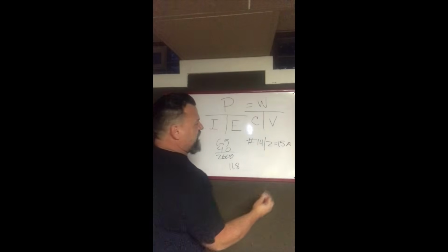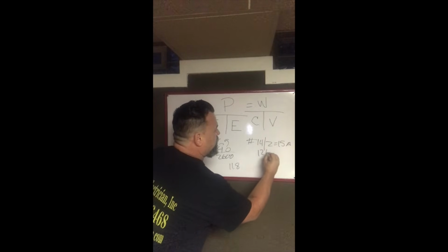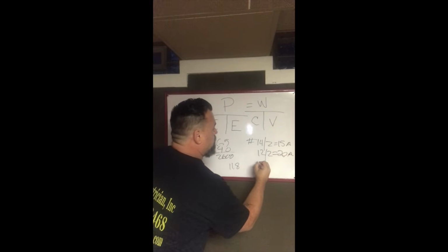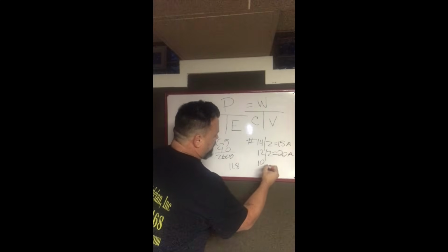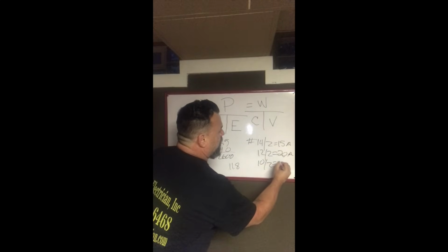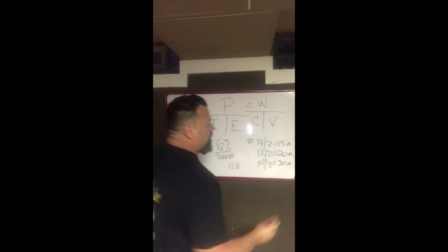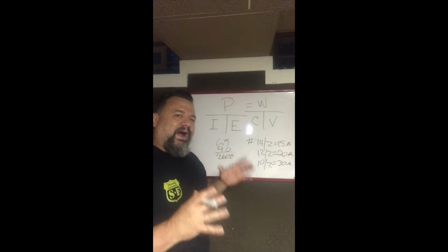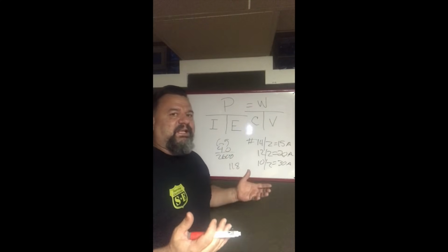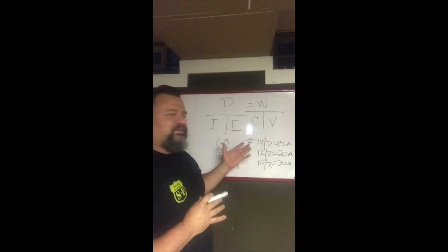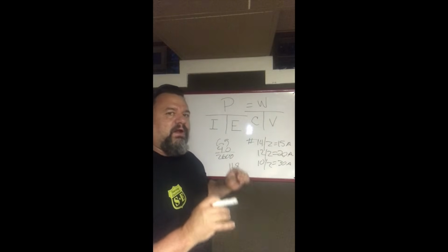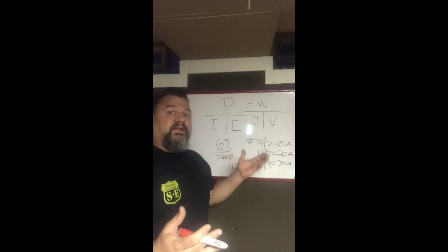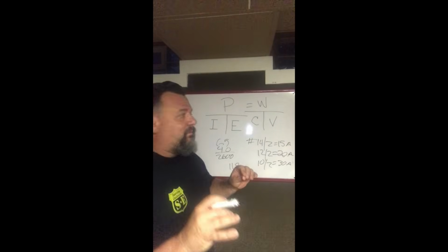Now, 14.2 is good for 15 amps. 12.2 is good for 20 amps. Number 10, call it 10.2, good for 30 amps. Now, why you would never do that? Number one, the wire inside of the fixture is only like 18 gauge. I don't even know why they even have it on a 15 amp circuit. The wire is smaller than the breaker size. Considerably, the light could catch on fire before the breaker trips. You want to get technical about it.